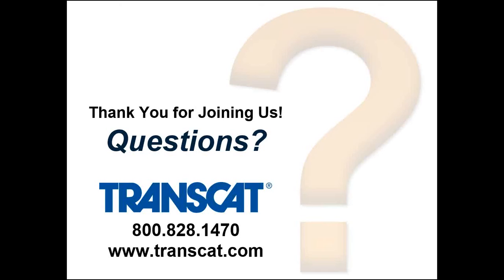What we do is we get into a tool that we've designed called PCS, and that's probability of conformance to the specifications. It's a tool that allows us to measure when we're into a guard band, when we're at a risk value, and quantify the risk as well. What that allows then is for our customers to make a decision rule on what values they want to have trigger adjustments, so that you're not optimizing every time, and you're not optimizing even at just 50% every time. It's optimizing at the right level based on the uncertainty, based on the tolerance of the instrument, and that can vary for each and every instrument. They can make one decision rule that allows us to catch that across the board when it enters the guard band at the level of risk they can accept. So 50%, without that tool, is still a little conservative. It's not fully optimizing.